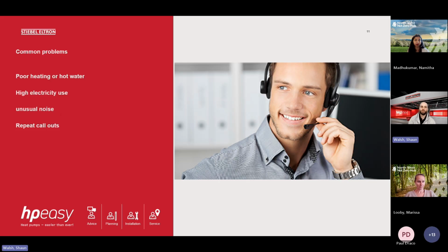Okay. So some common problems that you will come across are generally poor heating and hot water, high electrical use, unusual noise where the heat pump is running really loudly trying to overcompensate for something, and repeated call outs. These are some of the common problems that you will hear. The most common thing you will hear is people saying that the system's running, but they're not warm, or that bills are higher than expected, and it's not necessarily that the heat pump's broken. It's just not a comfortable temperature.